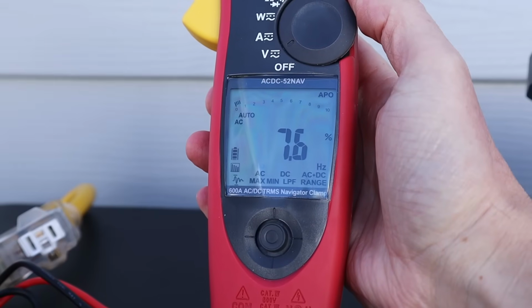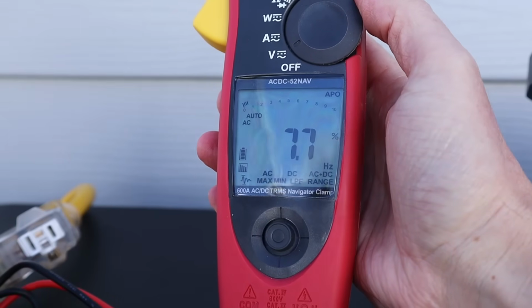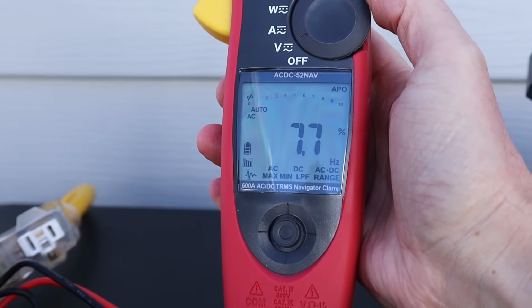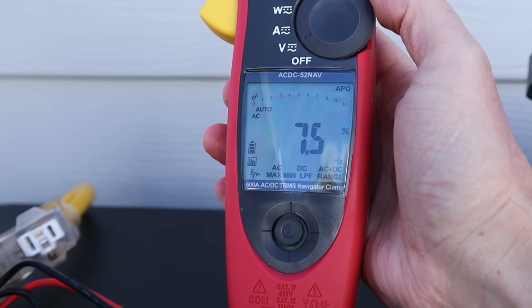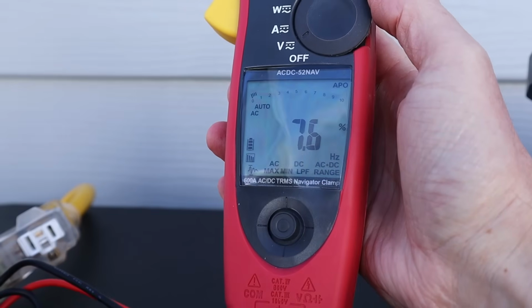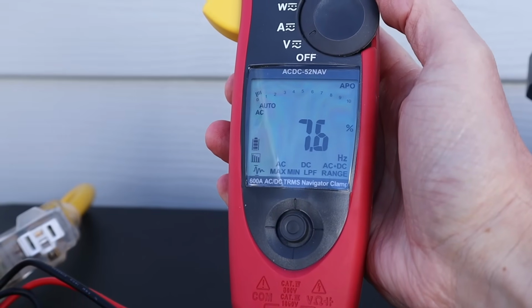With the generator under that 3,000 watt load, I'm measuring the total harmonic distortion again, and we're seeing 7.7 to 7.8%. It's jumping around a little, but that is really bad.